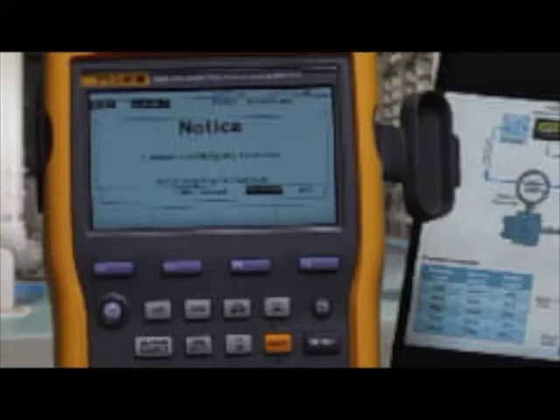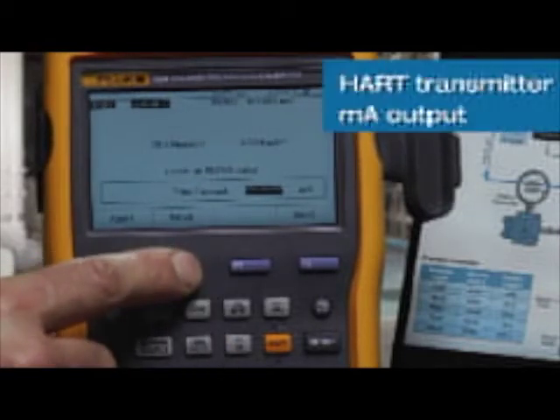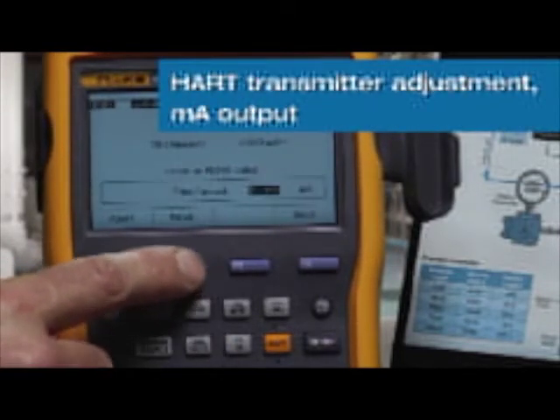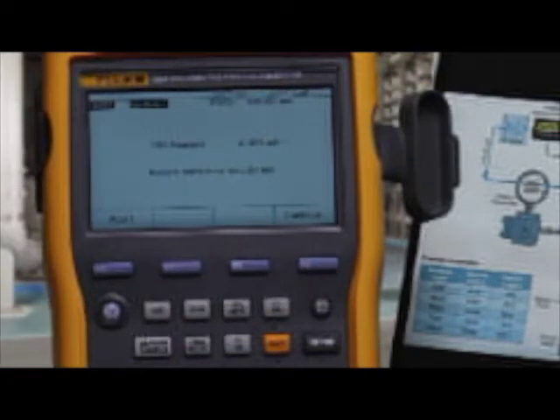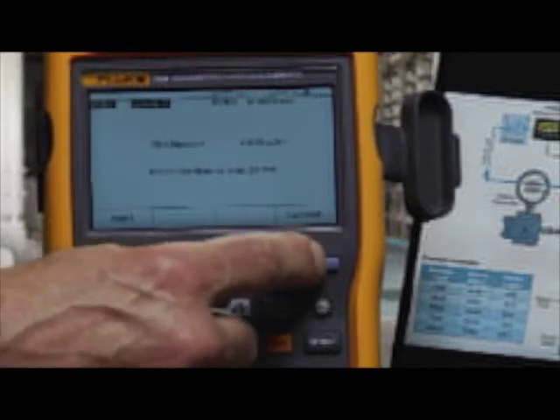First we're going to perform the output trim, fetch the 4 milliamp value, and send to make the adjustment. Continue to adjust the 20 milliamp point, fetch and send.